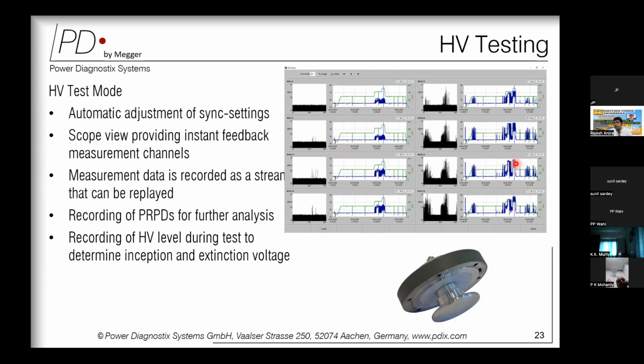Although it may not be very important because it is happening at the extremely high voltage, or the maximum voltage which we are applying, it is always good to know that the PD is occurring because of what kind of defects getting exposed in the GIS. So we will see in the next slide what additional measurements are also performed parallelly during HV test.